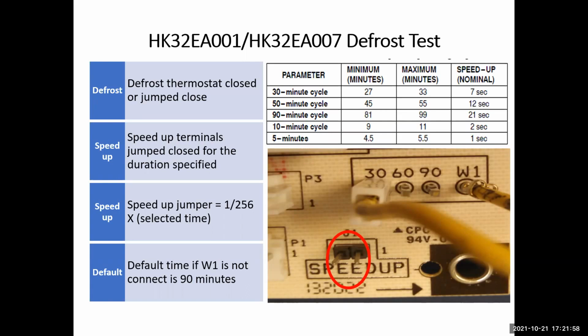Okay, so when the timer jumper is left off, and we're talking about the W1 jumper, and now it's set on 30. If this was just left off, it's going to default to a 90-minute compressor run. Using the speed up terminals, by shunting across the two posts for the duration that's on the speed chart, the normal operation of the control will be sped up by 256 times.